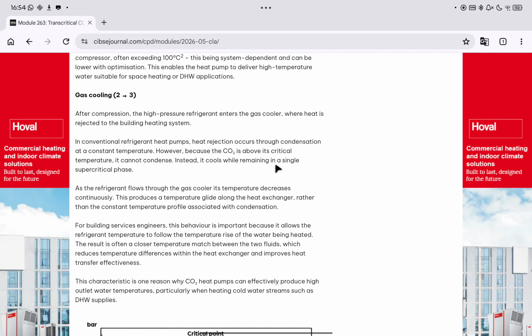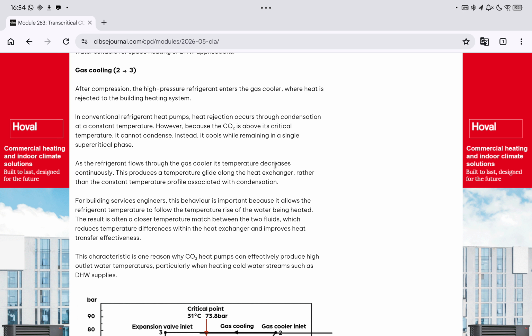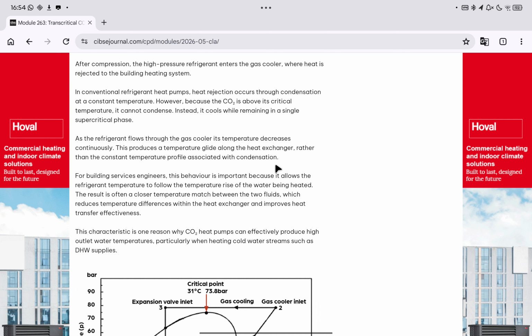For building services engineers, this behavior is important because it allows the refrigerant temperature to follow the temperature rise of the water being heated. The result is often a closer match between the two fluids, which reduces temperature differences within the heat exchanger and improves heat transfer effectiveness. This characteristic is one reason why CO2 heat pumps can effectively produce high outlet water temperatures, particularly when heating cold water streams, such as domestic hot water services supplies.